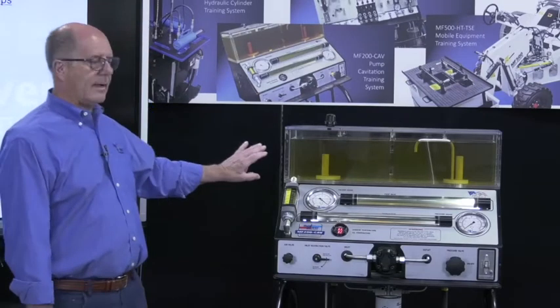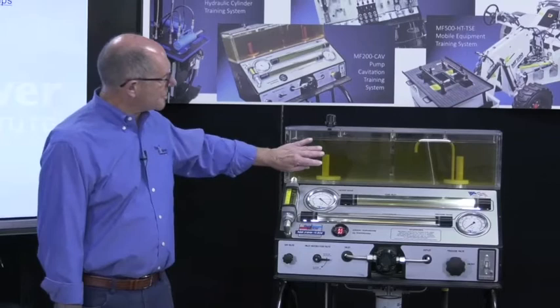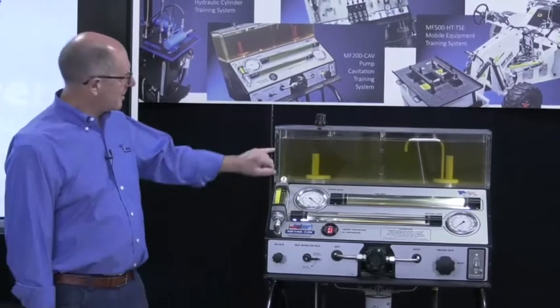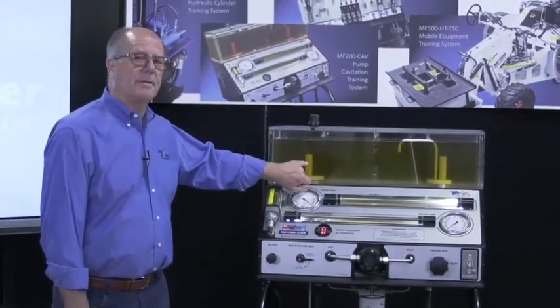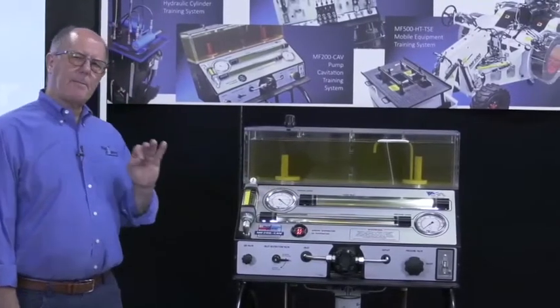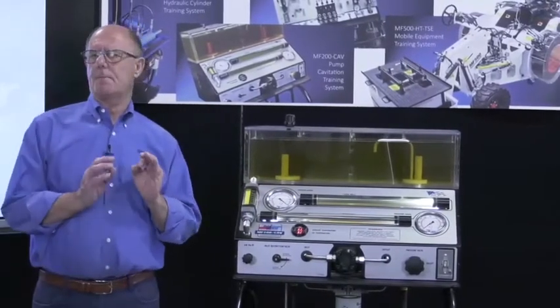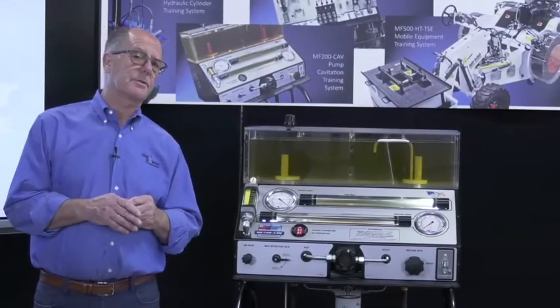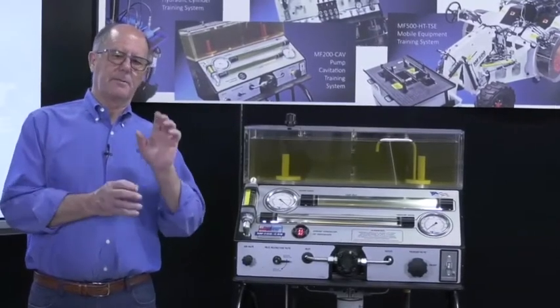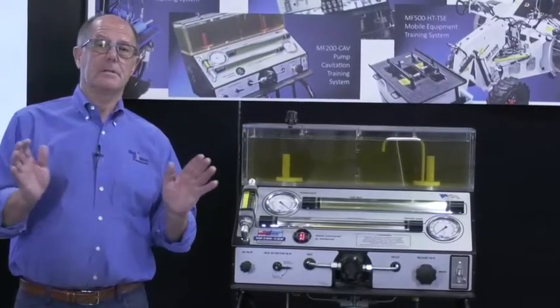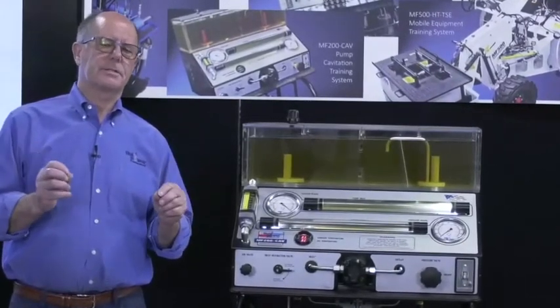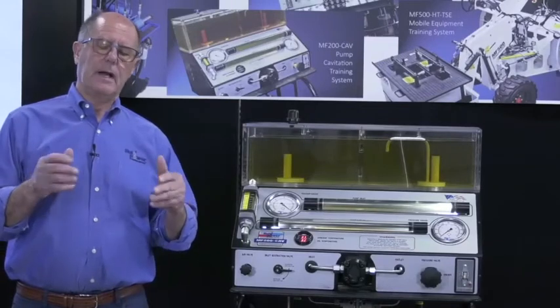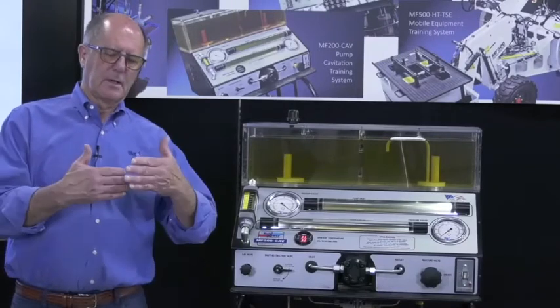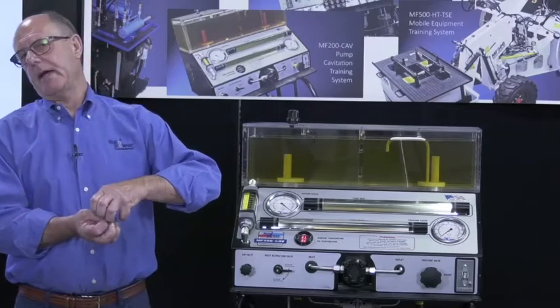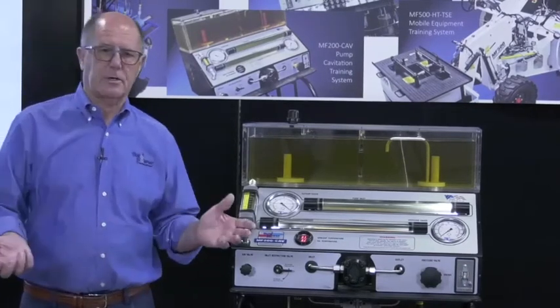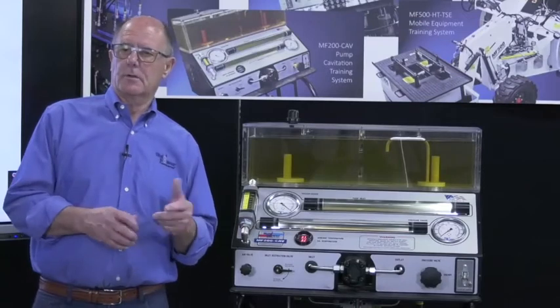So looking at this tank, it is almost impossible to see that there is 10% dissolved air by volume in this oil. Think of a bottle of pop. If you open a bottle of pop, like Sprite, let's say it's translucent, you'll notice that it goes from clear to bubbles. It fizzes. The reason why the dissolved air came out of the liquid is because you took the pressure off the liquid when you took the top off.